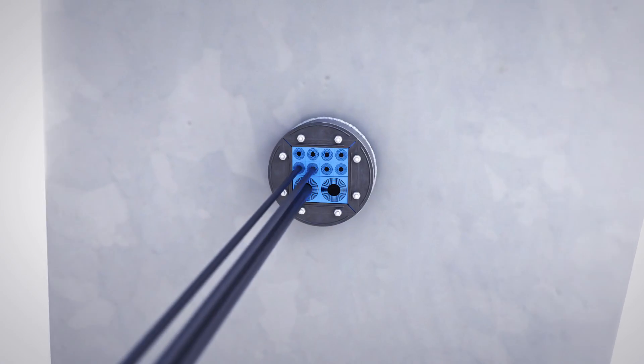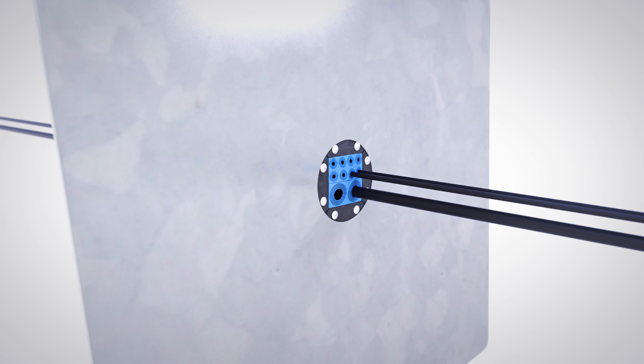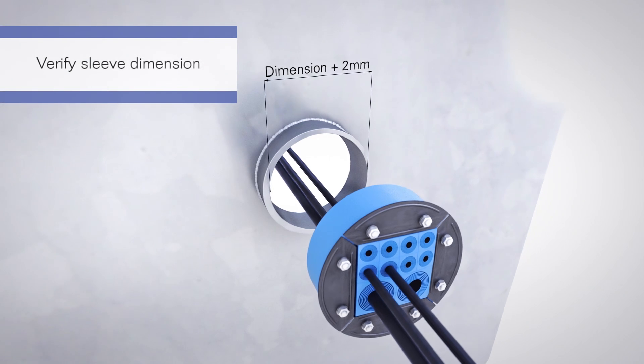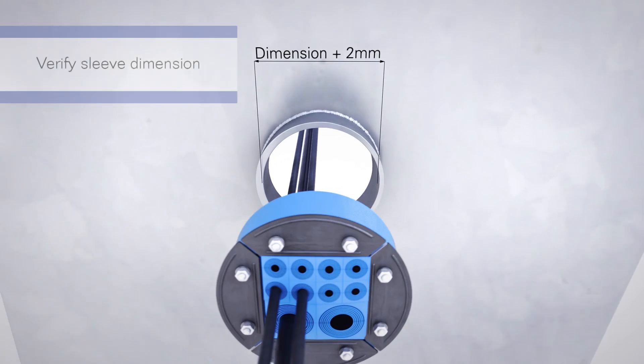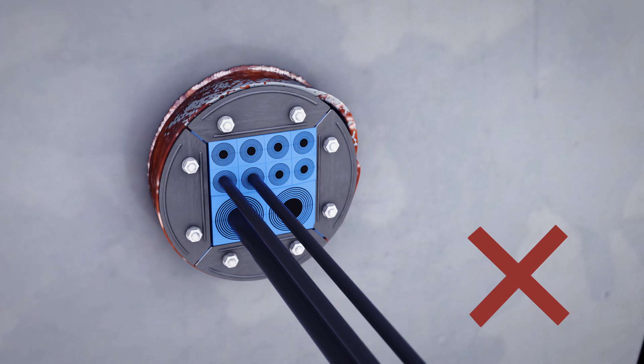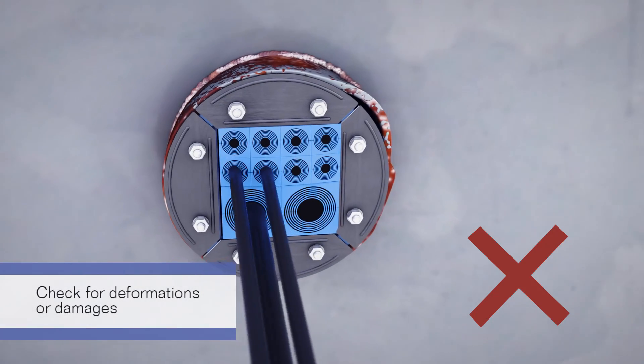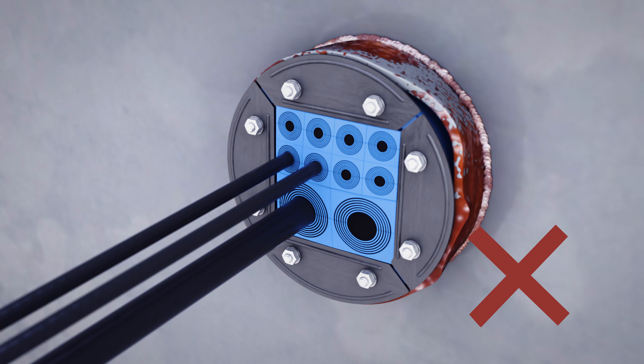This is how you check the installation quality for a round Roxtec seal. If possible, check the transit from both sides. If possible, verify correct sleeve dimension. Maximum internal dimension is sealing size plus 2 millimeters. Check the seal and sleeve for deformation or mechanical damage, such as excessive corrosion or incomplete welding.